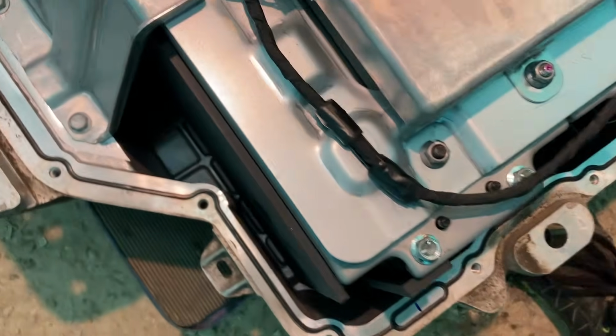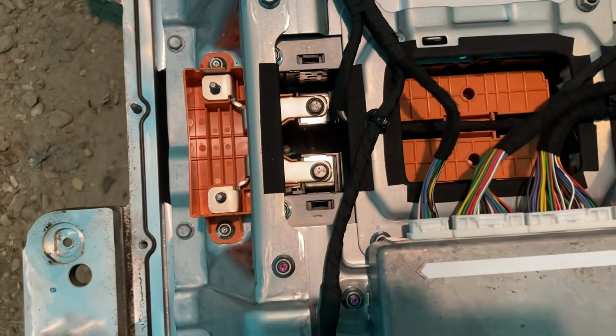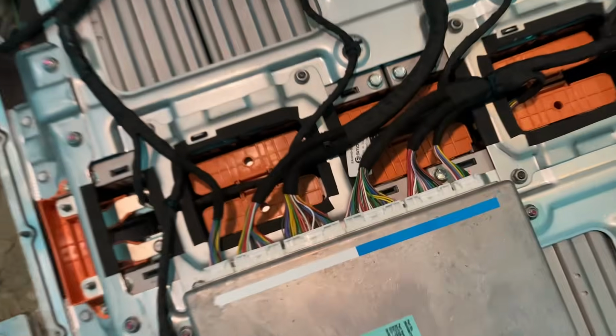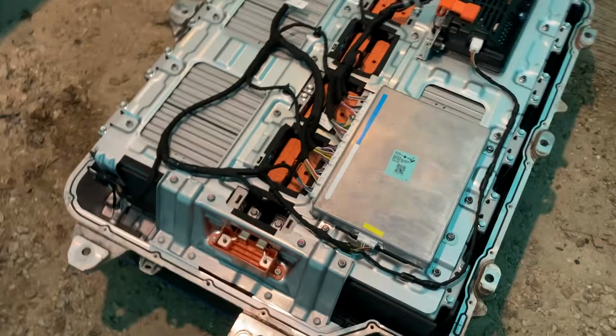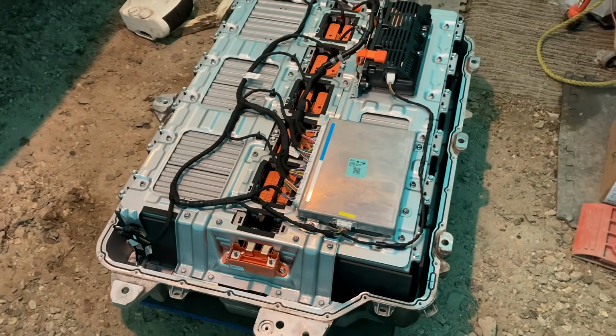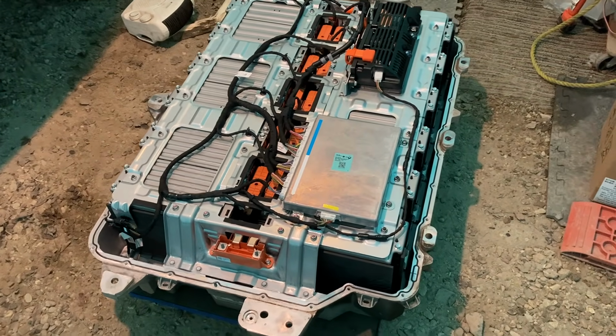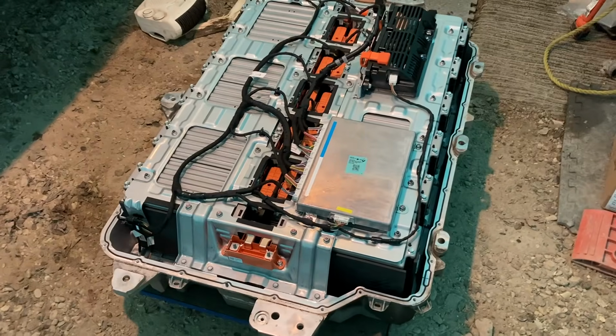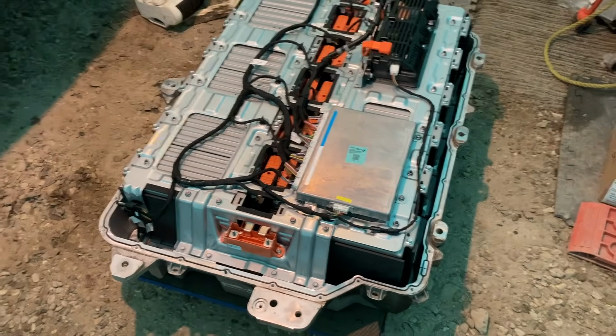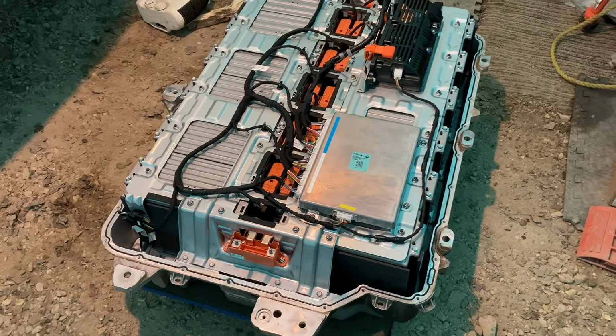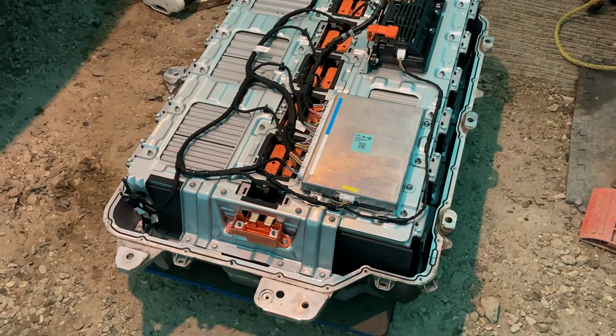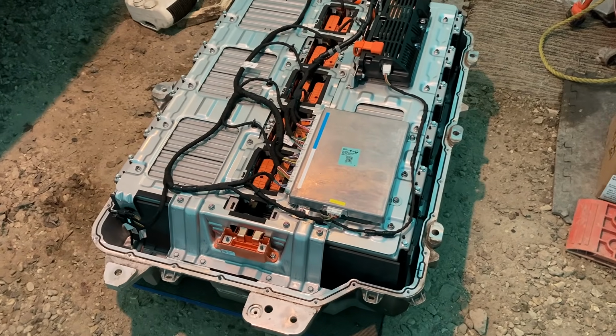No, a whole lot of nothing. The plot thickens - corrosion would cause it to misread, because we've got that cell showing it's about half a volt lower. What we need to work out is whether that cell is actually low or it's just a reading fault.